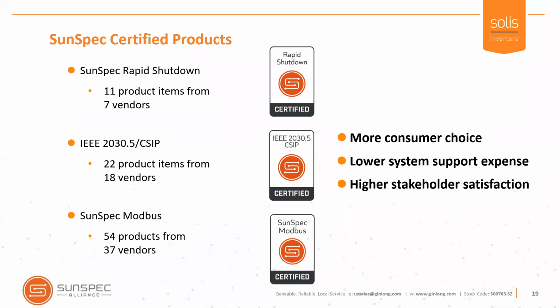The product that's been around the longest for us, SunSpec Modbus, has by far the largest share of the market here. I think you're going to see this increase quite a bit with the adoption of 1547 in the 2020 version. It pairs quite nicely with IEEE 2030.5 CSIP. Reason for that is SunSpec contributed the information models for 2030.5 CSIP, so we have 100% semantic compatibility between these two protocols. Why that's significant to you, and I apologize if some of this terminology is foreign, but hopefully in the near term it won't become quite so foreign.